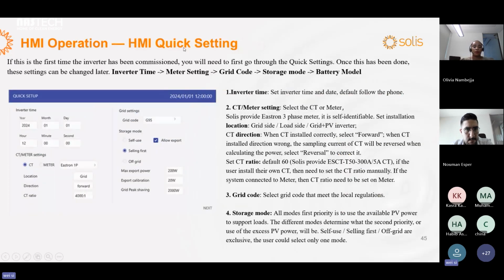We support quick setting for you when you first use the Solis hybrid inverter. You need to set the inverter time, maybe just follow your phone time, and set the meter or CT, the measurement and the location, the direction should be forward to the grid, and the CT ratio, and choose the grid code based on your region. And for the storage mode, you can choose the storage mode and the export power you allow. When this setting is finished, then you can use the hybrid inverter.